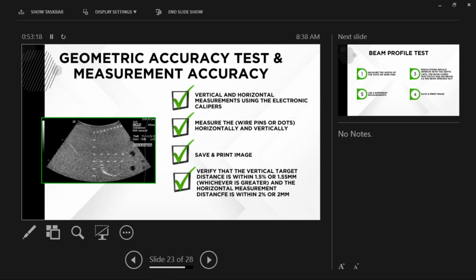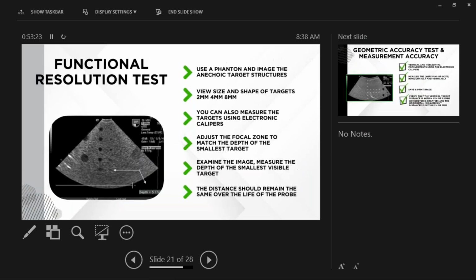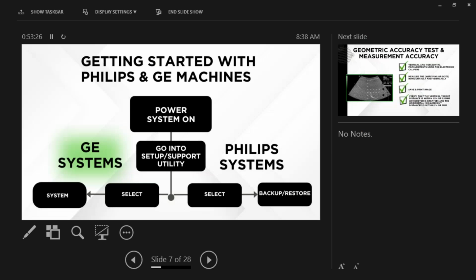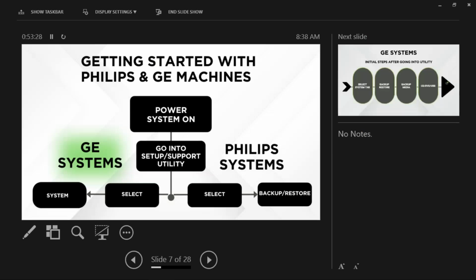I'll go here, see if it'll give it to me. There we go. So let's see if we can bring these image. All right. Here. So these are called wire dots. Each one of these wire dots have a measurement between them. This is 1 centimeter between this particular transducer. This is a 12L, so it's high megahertz, low depth penetration. So for this particular one, I would measure the distance from the near field to the farthest dot that I could see. My focal zone's over here on the right-hand side.